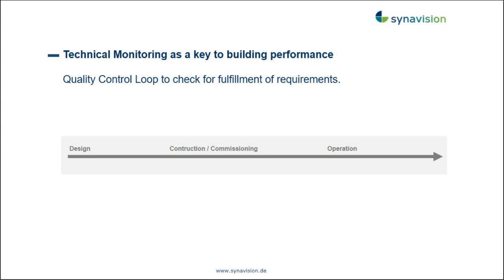Those 4 elements are, first, a set point. You always need a set point, a target value, like 500 grams of flour or 180 degrees Celsius in the oven. This is very important, and it's often neglected in buildings—those target values are often not precisely described.